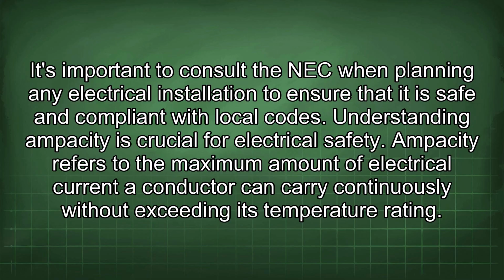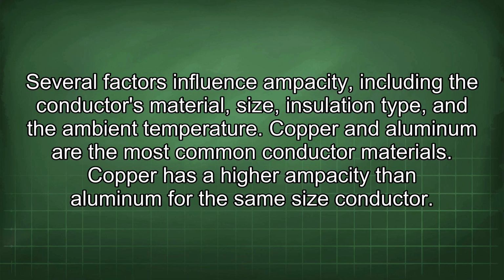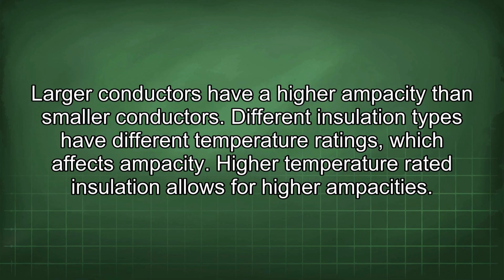Understanding ampacity is crucial for electrical safety. Ampacity refers to the maximum amount of electrical current a conductor can carry continuously without exceeding its temperature rating. Several factors influence ampacity, including the conductor's material, size, insulation type, and the ambient temperature. Copper and aluminum are the most common conductor materials. Copper has a higher ampacity than aluminum for the same size conductor. Larger conductors have a higher ampacity than smaller conductors. Different insulation types have different temperature ratings, which affects ampacity. High temperature rated insulation allows for higher ampacities.